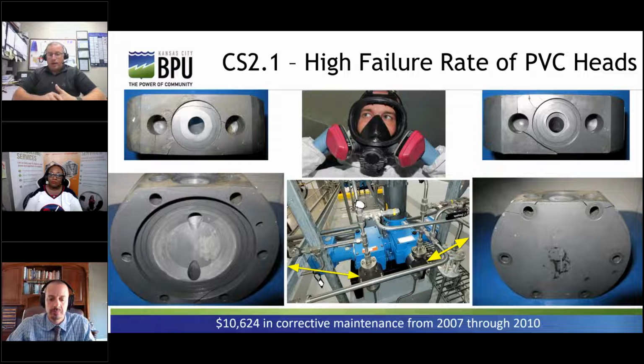At each failure, the head's aqua ammonia would leak out, and an ammonia sensor alarm would notify the operator a leak was occurring. The control system would close the supply valve to the metering pumps, and an operator had to immediately don a full face respirator and PPE and assess the problem, figure out how to rectify the problem and get the ammonia feeding again in less than 30 minutes.